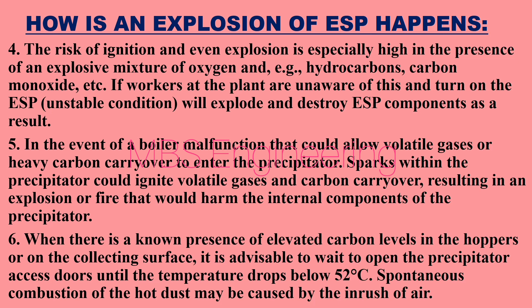Point 6: When there is a known presence of elevated carbon levels in the hoppers or on the collecting surface, it is advisable to wait to open the precipitator access doors until the temperature drops below 52°C. Spontaneous combustion of the hot dust may be caused by the inrush of air.